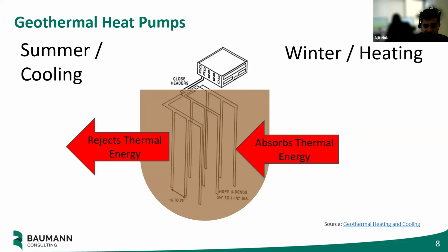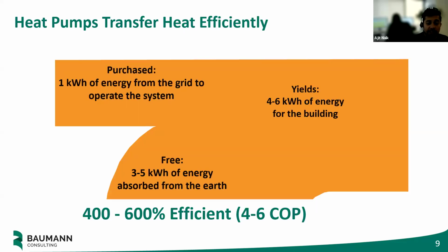It works in both directions, not just heating but cooling too - both times it can reject or absorb energy. So these units are a lot more efficient. As we discussed, their efficiency is tied to temperature, and when it gets really hot outside they consume a lot of electricity to cool, and when really cold they consume a lot of energy to heat. But ground source heat pumps, connected to the ground, never really get that cold in winter or that hot in summer, because they're connected to that thermal battery.